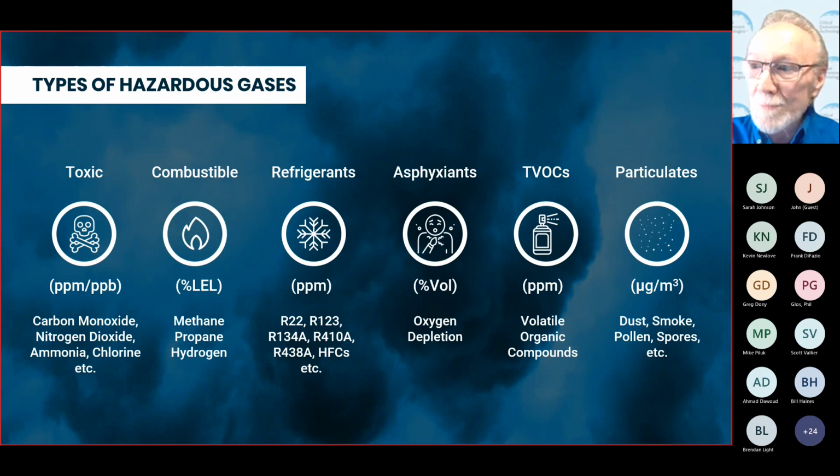Your mouth and nose, your breathing apparatus, is going to be approximately 2 to 3 inches off the floor, and that's where the heaviest concentration of that CO2 is going to be. And if that CO2 has reached a high enough level and pushed that oxygen towards zero, then brain death can happen in a matter of moments. So regulatory authorities are really concentrating and paying attention to the various gases that create an asphyxiant type atmosphere.